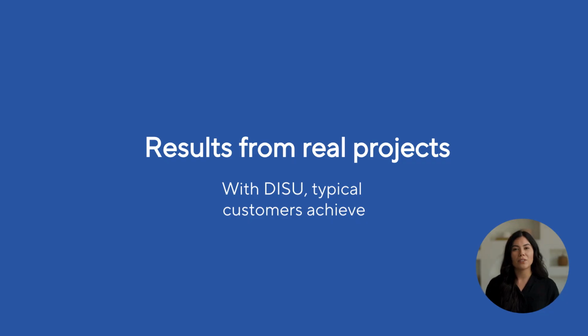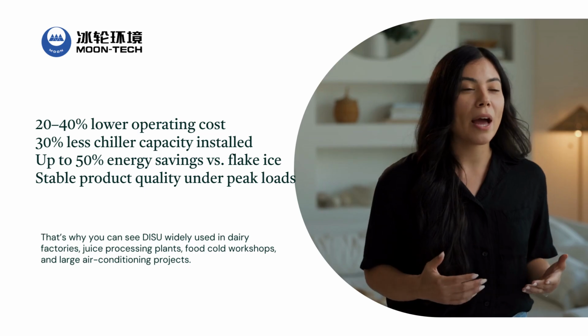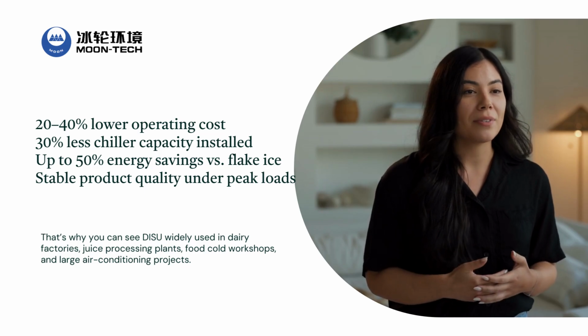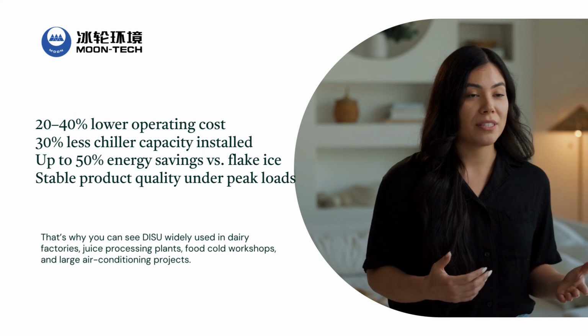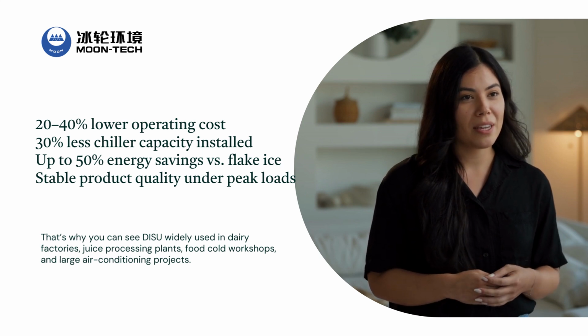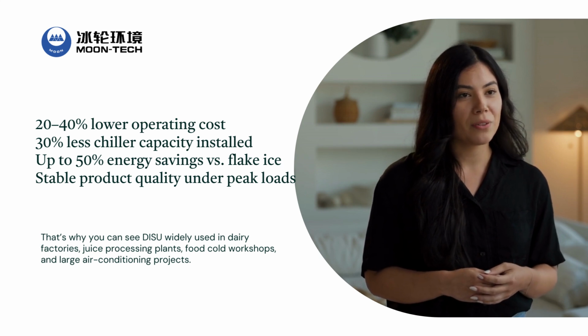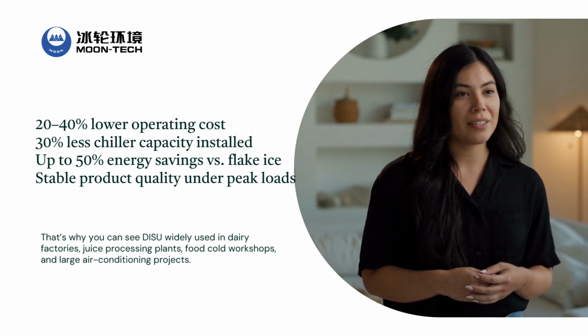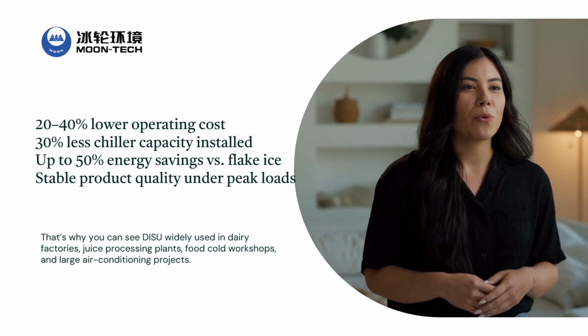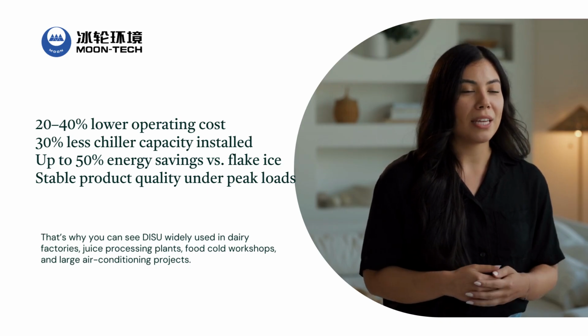Results from real projects with DISU: typical customers achieve, unlike traditional ice water or flake ice systems, DISU produces a special dynamic ice slurry, water with fine ice crystals. It cools like ice, but flows like liquid. This means it delivers 0-degree cooling with extremely fast heat exchange efficiency.